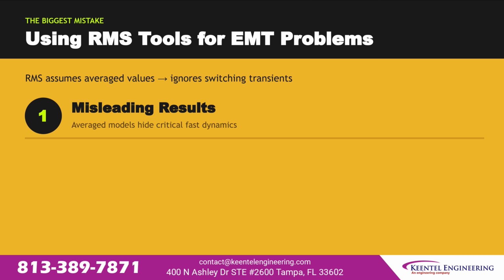The most common and most costly mistake in modern power system studies: using RMS tools to analyze problems that require EMT. RMS assumes averaged values. It ignores switching transients by design. That assumption produces three failure modes. Misleading results: the average model hides critical fast dynamics. Your study shows stable. The project is not.